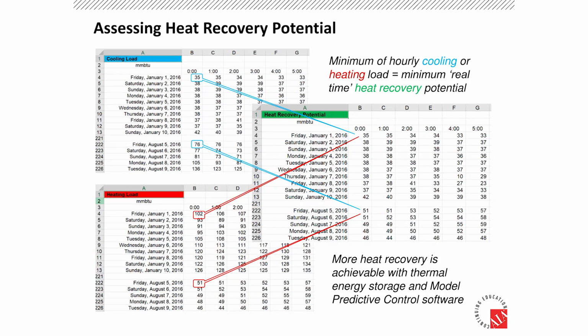So if you want to know the opportunity for heat recovery through a heat pump at your building, house, or anywhere, here's a simple method. If you know, every hour, how many BTUs of heat you need and how many BTUs of cooling you need, you simply compare the two for every hour. This example shows a winter month and a summer month. In winter, obviously you need more heat than cooling. Houses might not have any cooling, but buildings like this will even have cooling in the dead of winter, so you just take the lower of the two numbers.